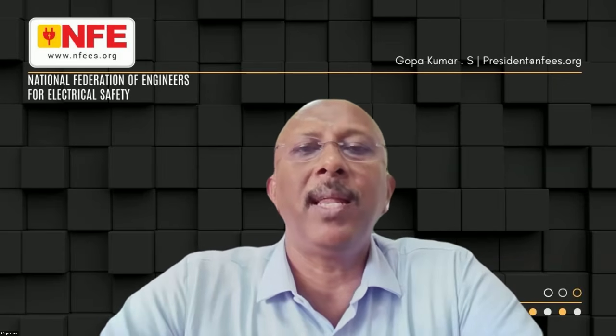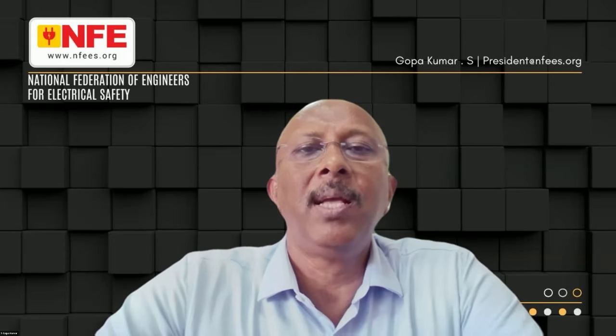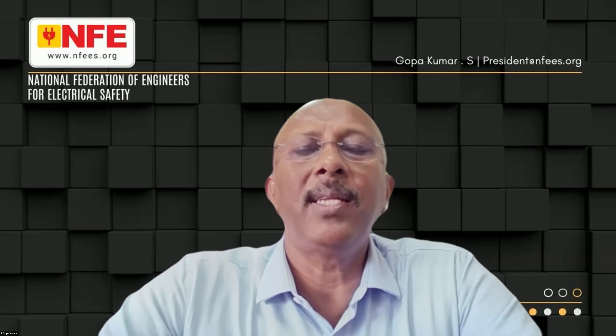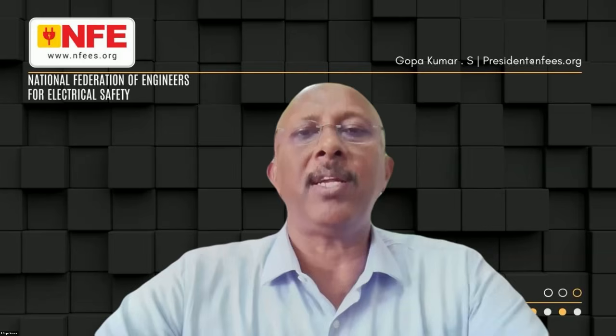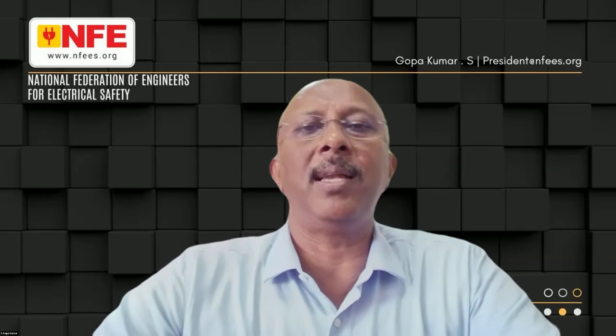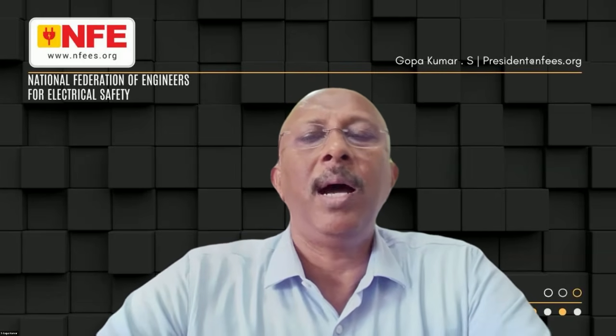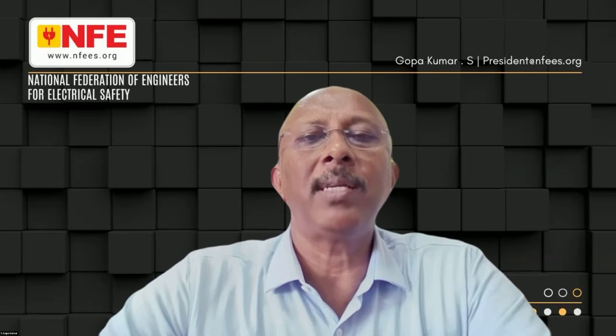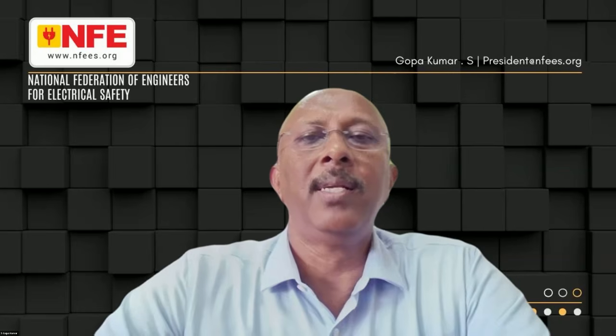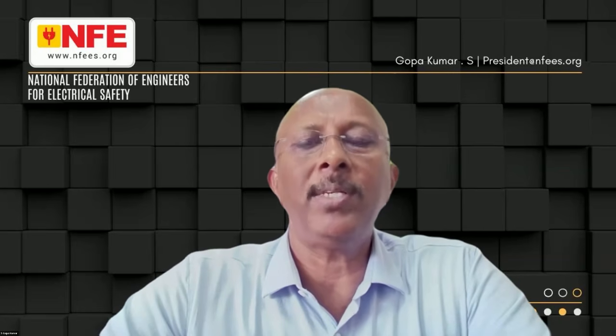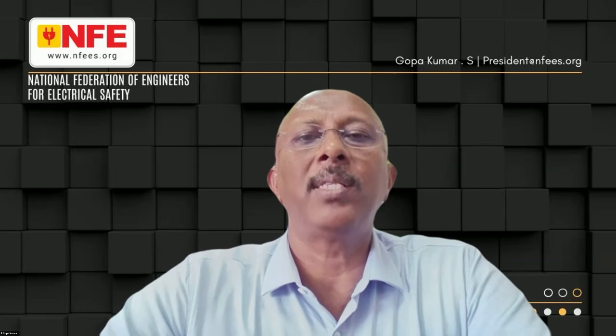But for sure, NFE can help you. Normal IT is, for example, the UPS manufacturers claiming that I have IT and supply the UPS with an isolation transformer at the secondary. This is number one. Number two, isolation transformers, and the manufacturer says I need a separate earth pit. This is not medical IT. Sometimes only the isolation transformer with an insulation monitor is given.